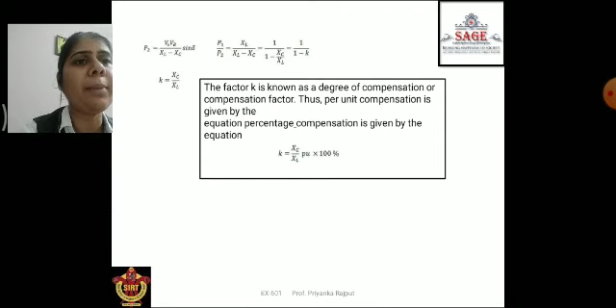Now, XL is the total series inductive reactance of the line per phase, and XC is the capacitive reactance of the capacitor bank per phase. In practice, K lies between 0.4 and 0.7. For K equal to 0.5, P2 upon P1 is equal to 1 upon 1 minus K, which is 1 upon 1 minus 0.5, and its value is 2. Thus, the power transfer is doubled by 50% compensation.